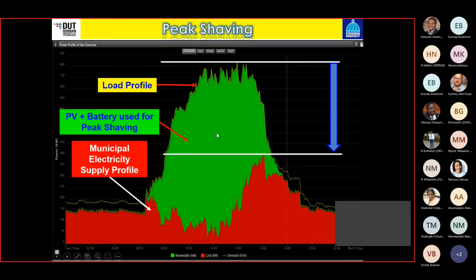Look at the next graph, just to give an example. Here's a customer's day load profile. The bottom white line is where, let's say, we want to shave anything above that line. So your battery system will supply the load above the line, and the customer will pay lower on his network demand charge and network access charge. So typically you can save on those charges during the summer months, while in the winter months you can use energy arbitrage. You can use that as a business model for his battery system, together with other aspects such as supplying his load or assisting during load shedding.